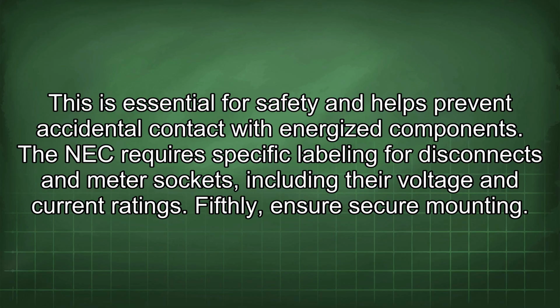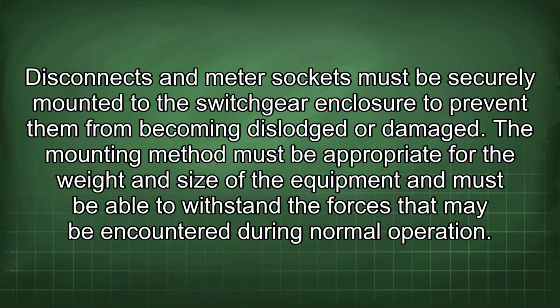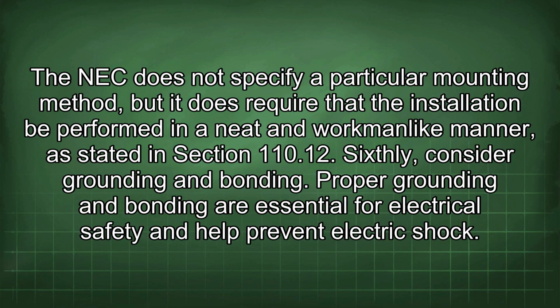Fifthly, ensure secure mounting. Disconnects and meter sockets must be securely mounted to the switchgear enclosure to prevent them from becoming dislodged or damaged. The mounting method must be appropriate for the weight and size of the equipment and must be able to withstand the forces that may be encountered during normal operation. The NEC does not specify a particular mounting method, but it does require that the installation be performed in a neat and workmanlike manner, as stated in section 110.12.